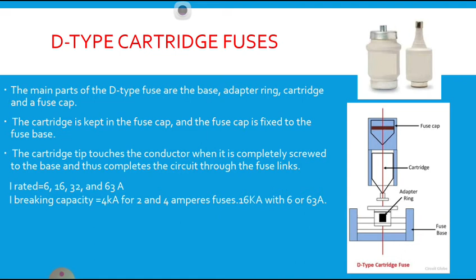If the fault lasts only a short period, nothing will happen; it may not melt. If the fault is sustained for a long period, it automatically melts itself. The major advantage of the HRC fuse is that it clears low as well as high fault current. The HRC fuse has a high speed operation, whereas we have seen the rewirable fuse is a low speed operation, so this overcomes that disadvantage.